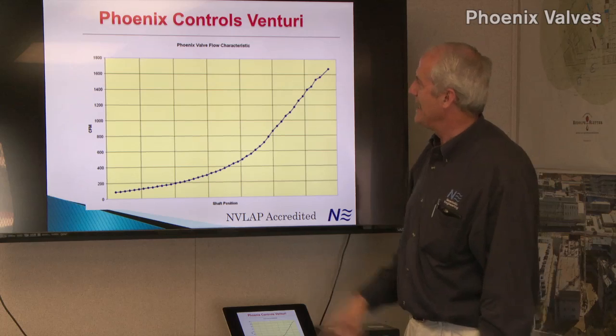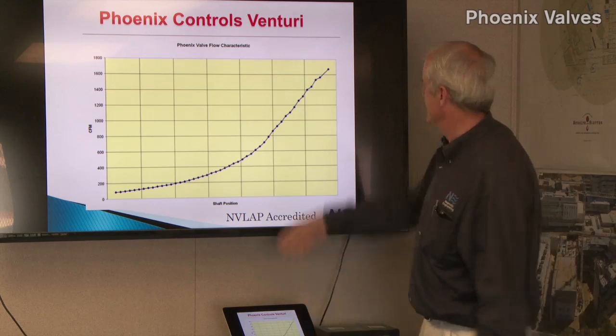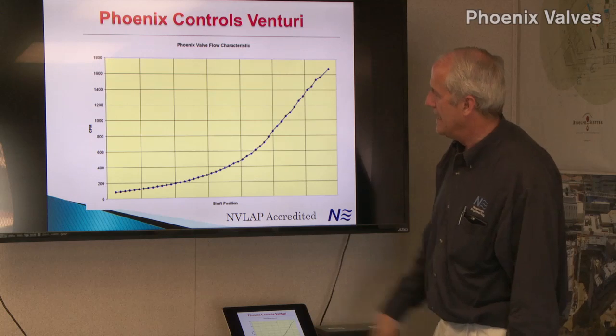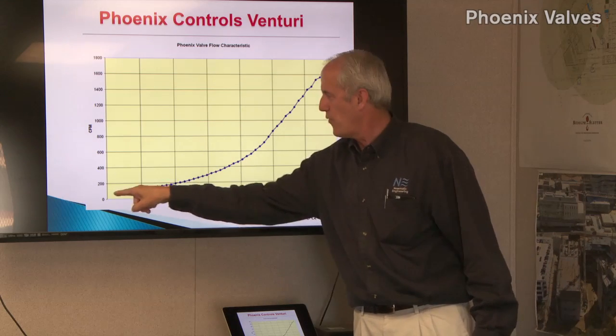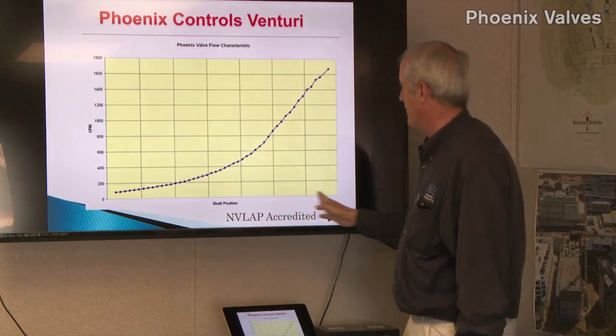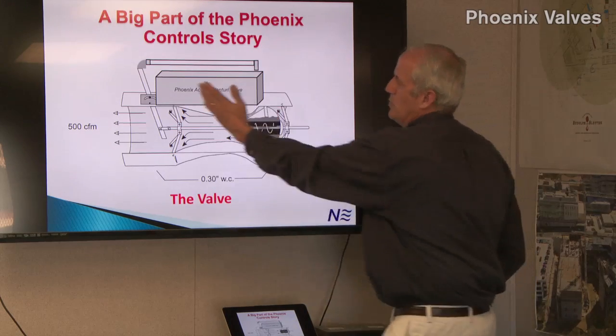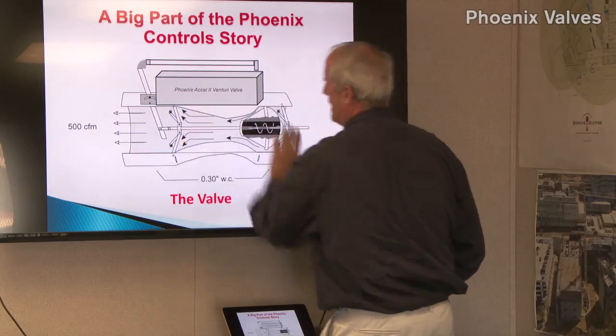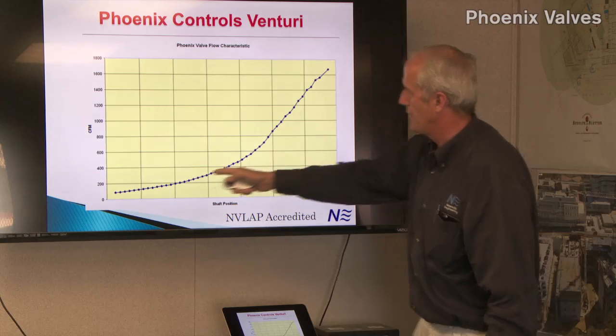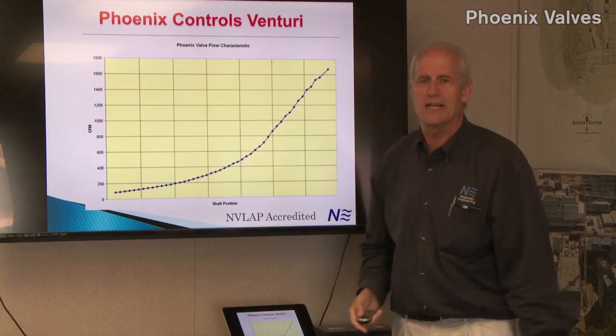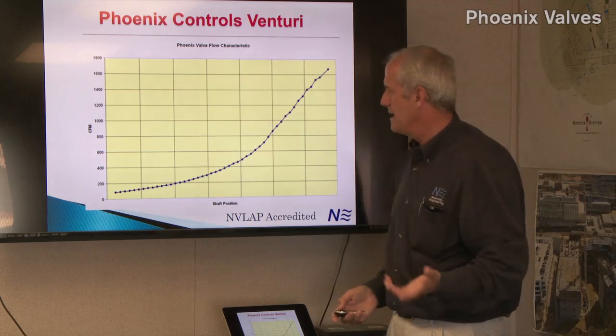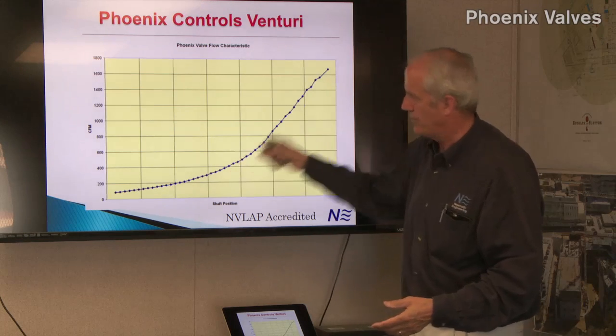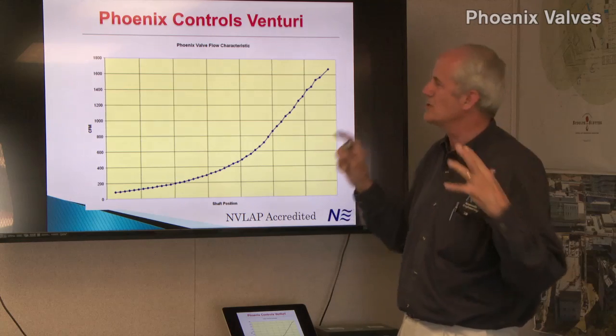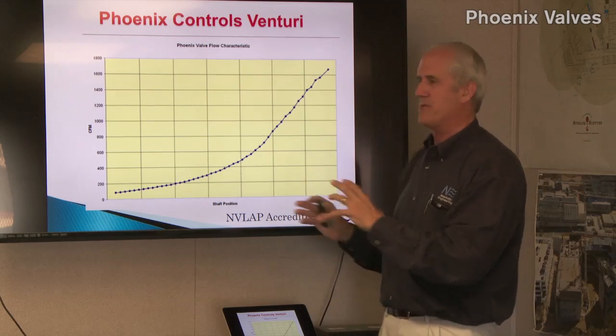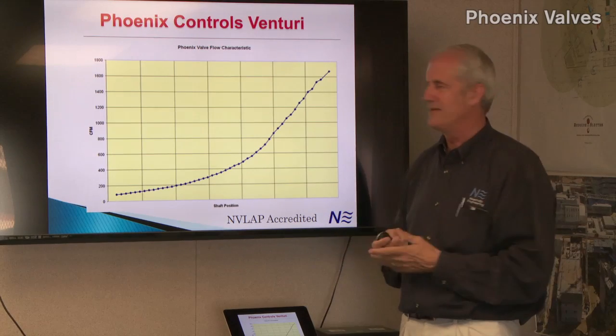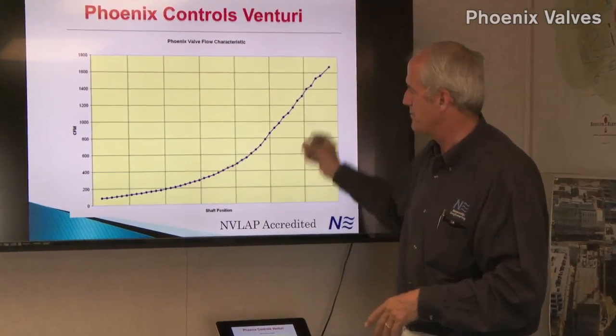Every VAV valve we make is characterized on a flow station. This is a sample of one of our 12-inch valves. We measure the flow at 48 different points as we move the shaft of the valve. So on the previous slide, we move this shaft, so we move the cone in and out, and at each one of those 48 positions, we take a measurement to see what the flow actually is. We also take multiple pressure readings for most of these settings. So we actually take over 120 different readings for every valve we make. We didn't just do it once, we don't just do it occasionally. Every VAV valve we make gets put on a flow curve like this.